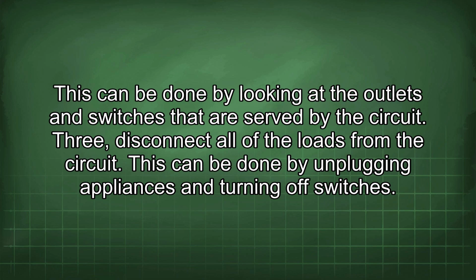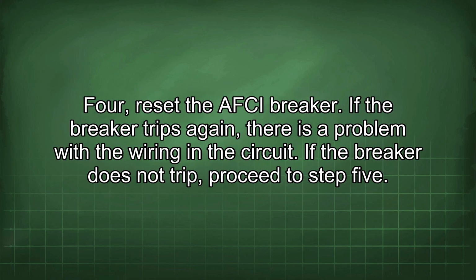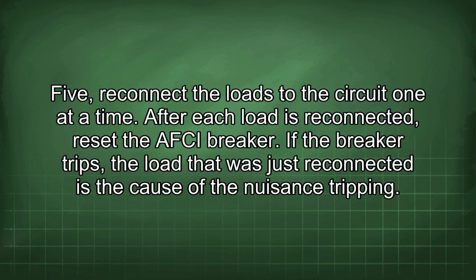3. Disconnect all of the loads from the circuit. This can be done by unplugging appliances and turning off switches. 4. Reset the AFCI breaker. If the breaker trips again, there is a problem with the wiring in the circuit. If the breaker does not trip, proceed to step 5. 5. Reconnect the loads to the circuit one at a time. After each load is reconnected, reset the AFCI breaker. If the breaker trips, the load that was just reconnected is the cause of the nuisance tripping.